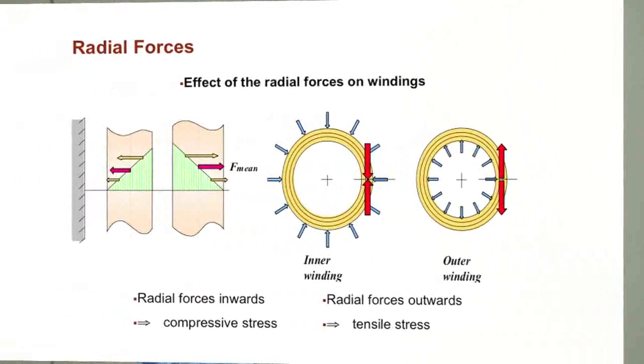And it's also very important that the centers of the windings are very close to each other. Because if there is a big difference in the centers of the windings, when you have a short circuit event, it's going to try to drive that apart. So when we make transformers, the centers of the windings have to be within a few millimeters tolerance. If not, then during a short circuit event, it's really going to exaggerate that difference.